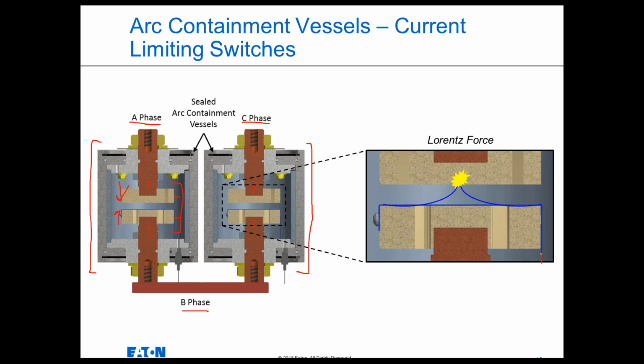What happens when the arc quenching device receives that trigger signal is it dumps current into this blue wire. This blue wire runs up the side of each of the lower contacts, across the top of each of the lower contacts, and then doubles back on itself and returns to the trigger board. So when the device activates, the trigger board dumps current into this wire, and that current flows through the wire.